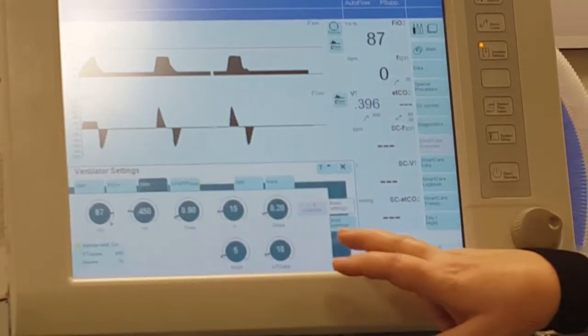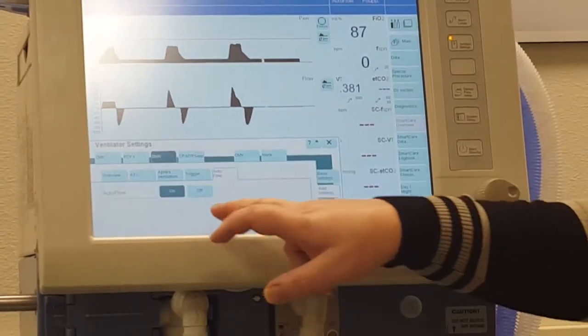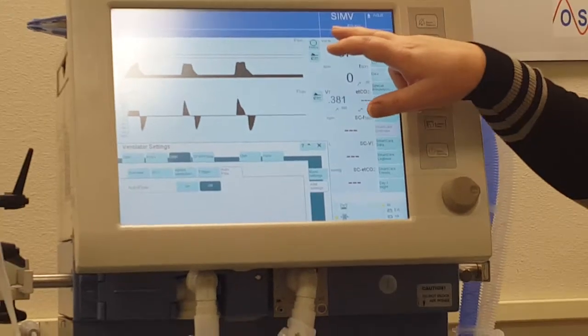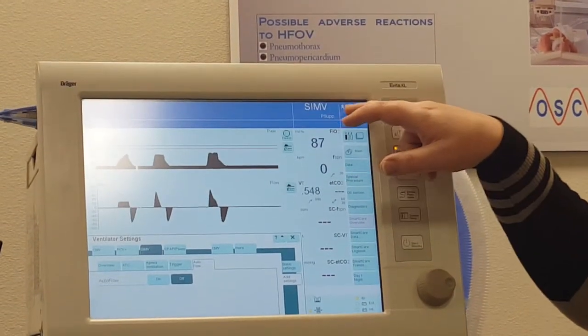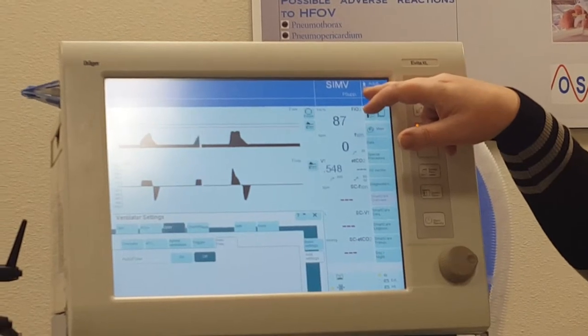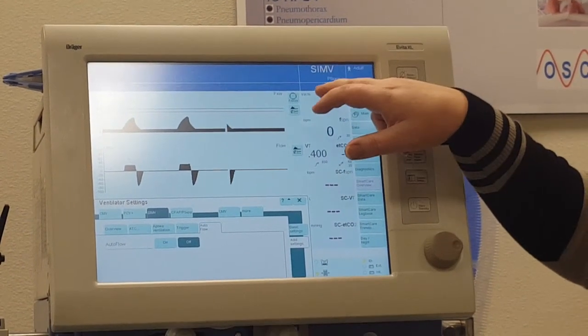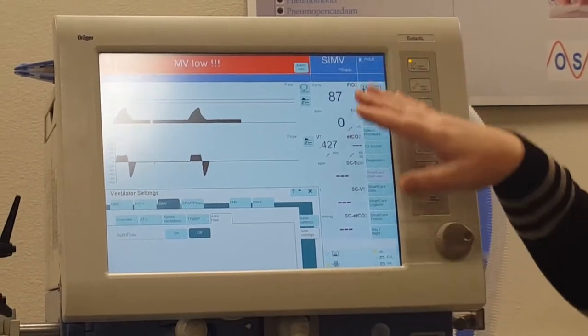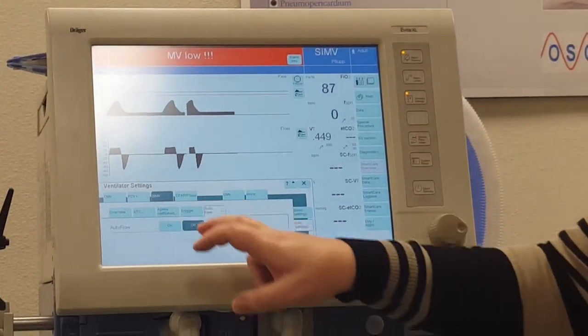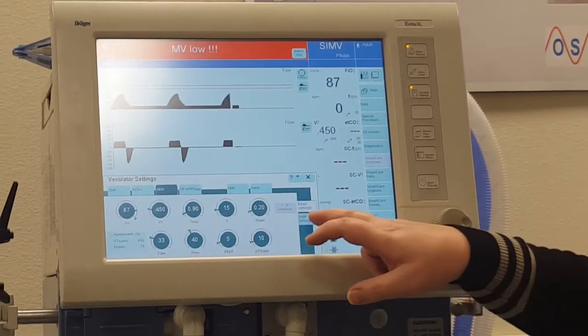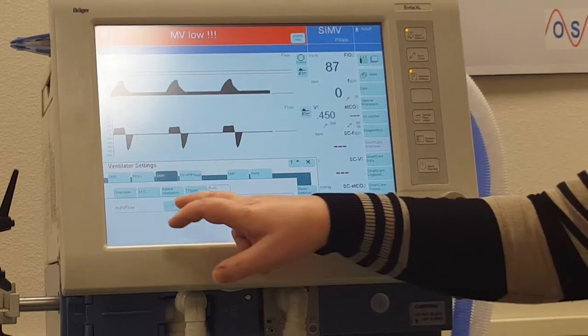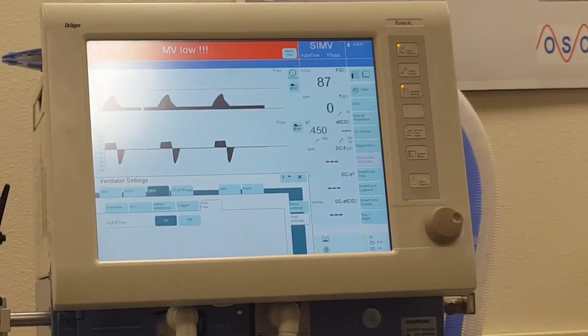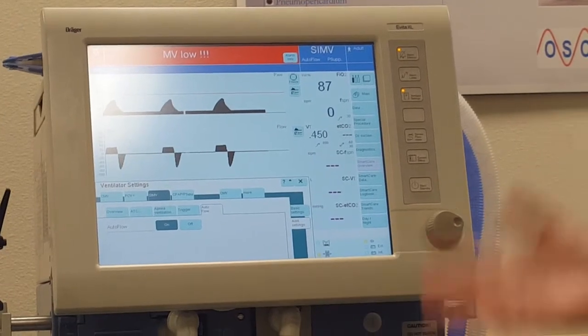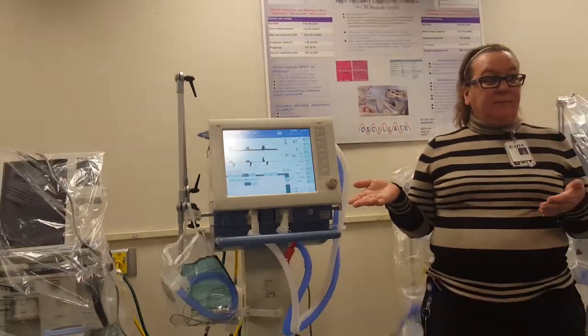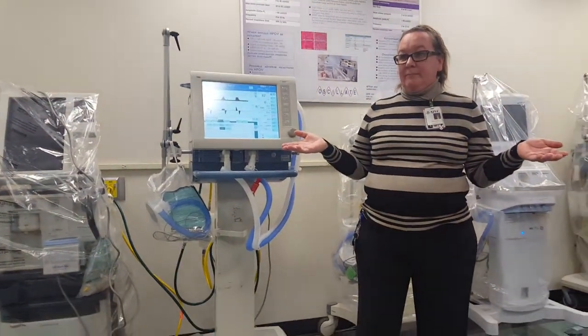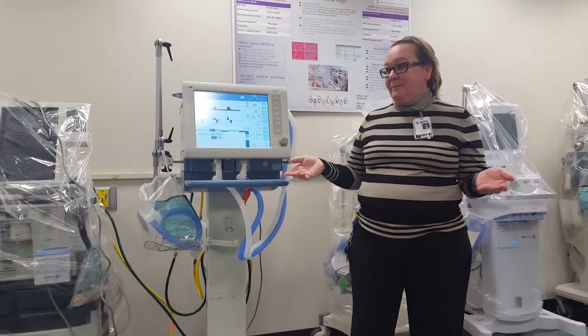So if I want to go to SIMV VC, I'm going to go to additional settings, go to auto flow, turn it off, hit that, and now it's just SIMV VC. It says the word pressure support because that's something you can set in it. We'll talk about that more later. So now I'm in SIMV VC because auto flow's off. If I want to go to SIMV PRVC, I just go back to my SIMV tab, additional settings, auto flow, on, confirm, and now I'm back in SIMV PRVC. So basically, auto flow on the DRAGER means PRVC. Don't worry about why they gave it some crazy name. Just know that it means PRVC, okay?